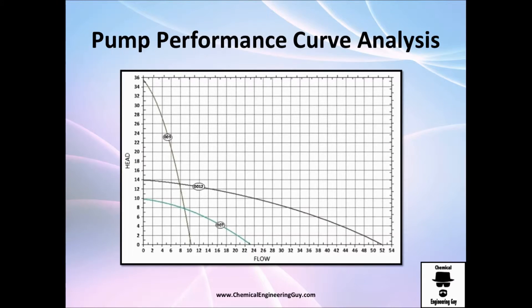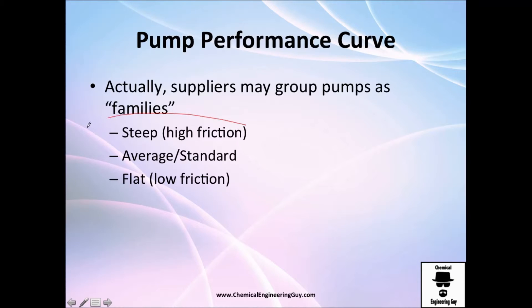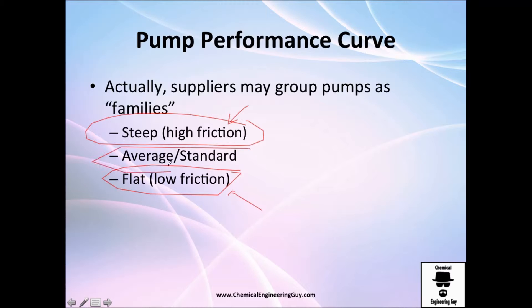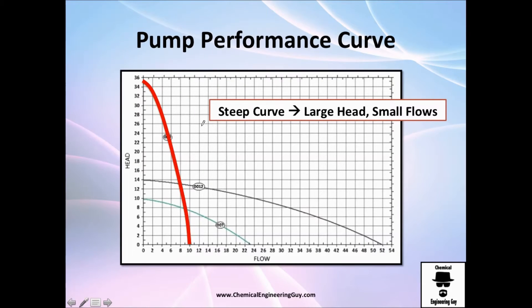There are many other types of pump curves. For example, this pump right here is very steep, and this other pump is very flat. All pumps that are very steep fall into one category, and all pumps that are very flat go into another. A steep curve is associated with high friction and a flat curve with low friction, with a standard curve somewhere in between — not too flat and not too steep.